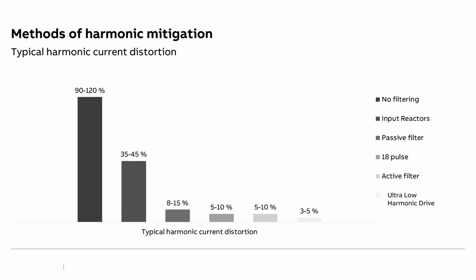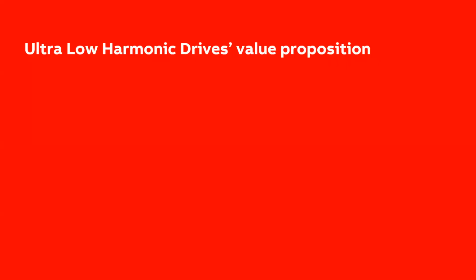Then we have passive or active filter, and then a premium solution, which is the ultra low harmonic or the active front end. With the active front end, we can achieve harmonics of even below 5%. We can achieve harmonics of approximately 3% also with an ultra low harmonic drive. So we'll see what are the advantages of this new technology, the active front end technology.